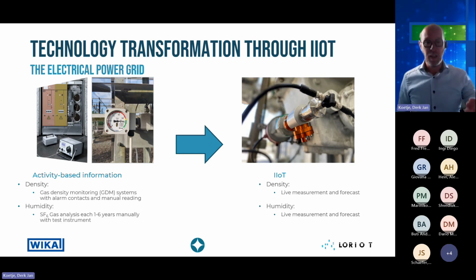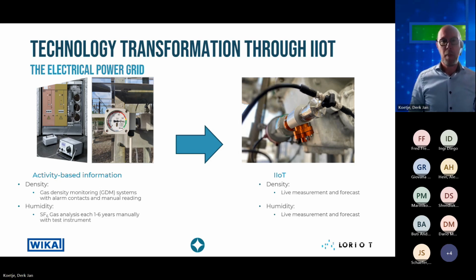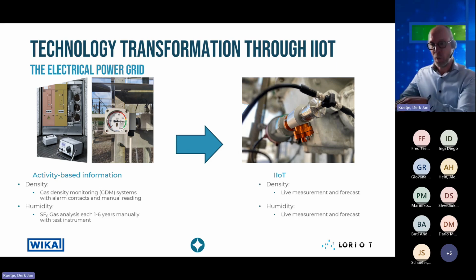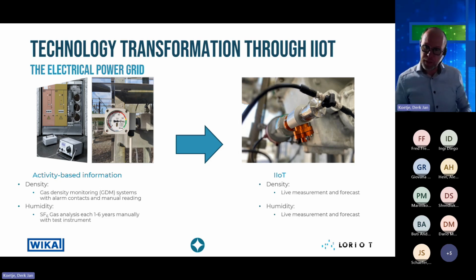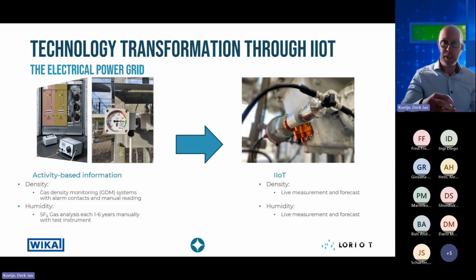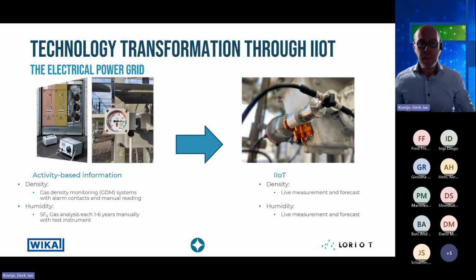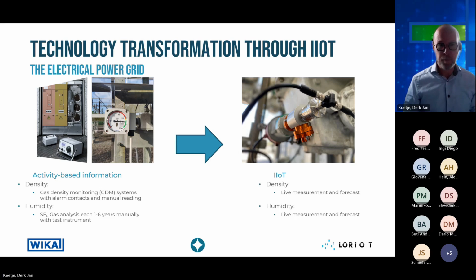You need live measurement data, and you need forecasting. With the forecasting that WIKA provides in its solution, you're able to predict when you need to schedule maintenance. So it's no longer time-based maintenance, it's now condition-based maintenance. That's a completely different approach to maintaining your substation and your switchgear.